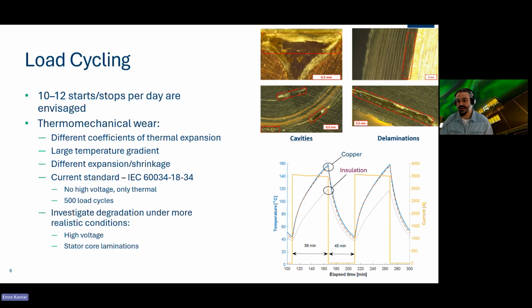What is load cycling? Some of you may not know what the term means, but it's the mimicking of starts and stops of the machines, exposing the stator insulation to temperature gradients so we can detect some aging or failure mechanisms.